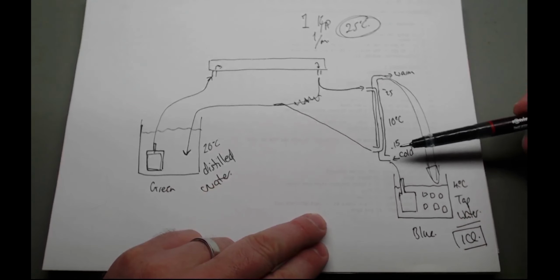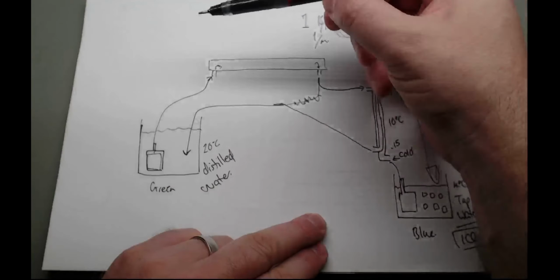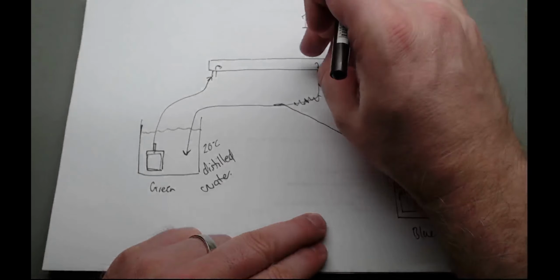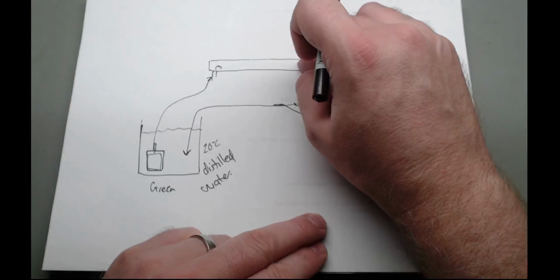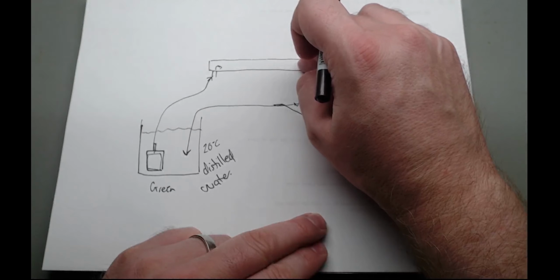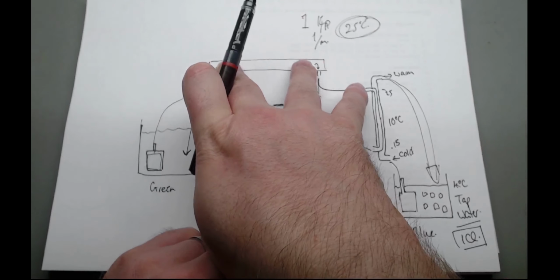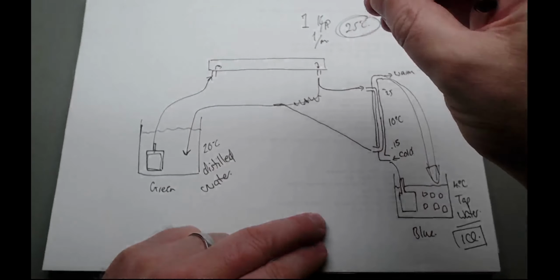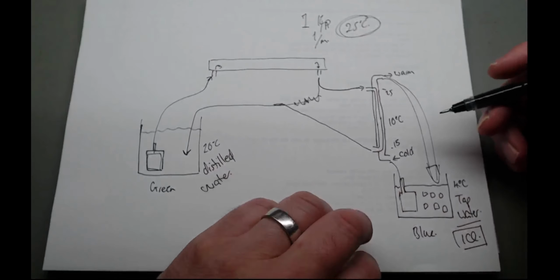Otherwise, what will end up happening is this water will get too cold. I'll then start getting condensation on this tube, and then I can end up getting those shorts, because this tube's running, was it 8,000 kV, 20 kV, a large number of kilovolts. Yeah, really high voltage across it. You don't want water beading on the outside of the tube. So you don't want the water too cold.